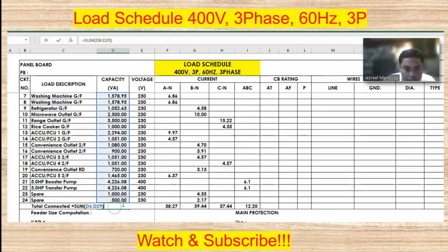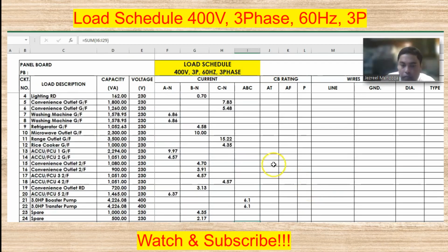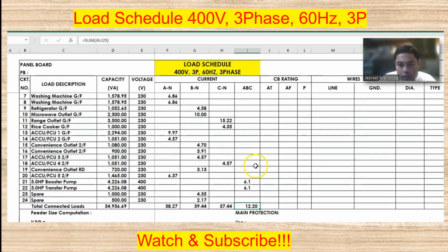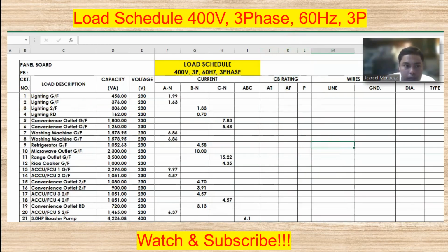Okay, and then we have total capacity, it's 34.93 amperes. And then after that, we're done balancing the loads. Our main concern again is to have this circuit protection, the circuit breaker. Lagyan natin ang rating. Again, for the washing, for circuit number 1, let's use 20 amperes.